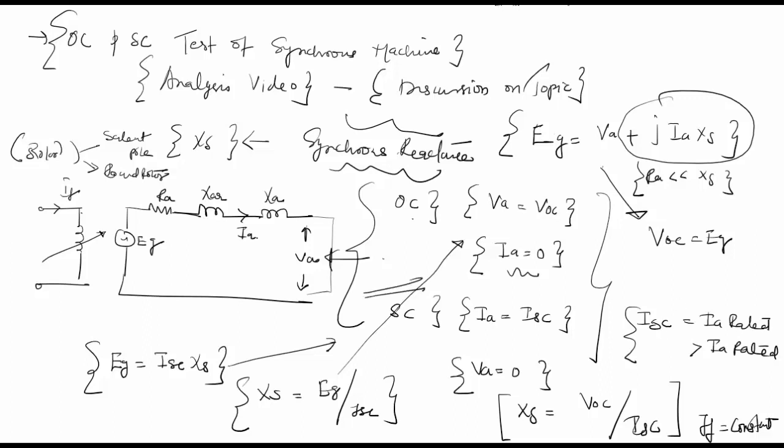It is seen that during the open circuit since IA is equal to zero, the losses happening are mainly core loss and friction and windage loss only.